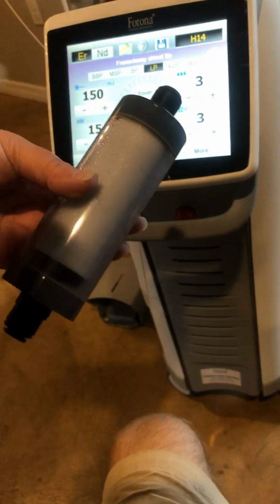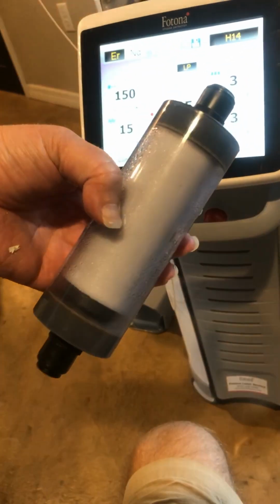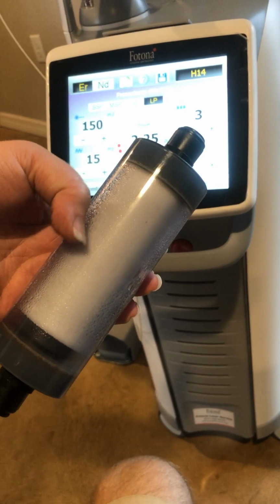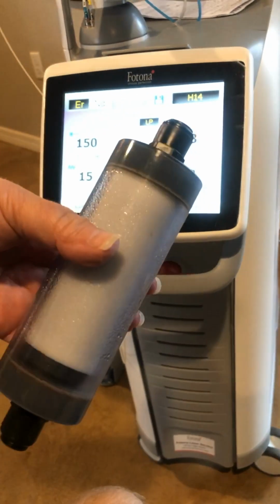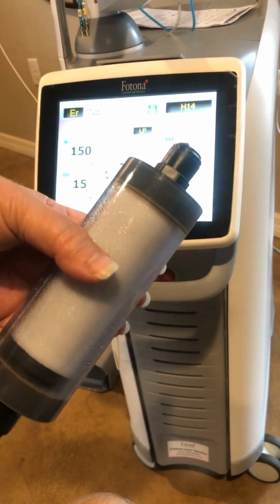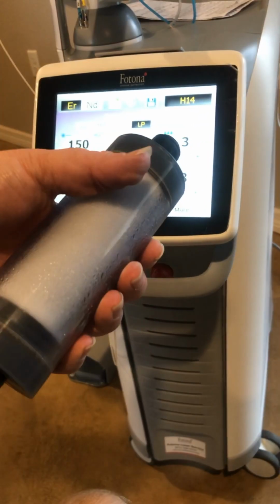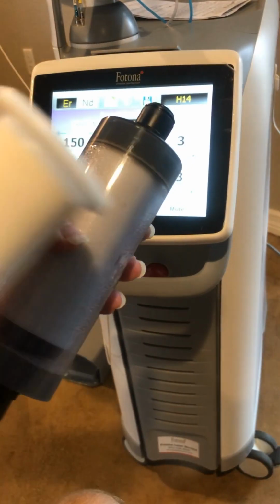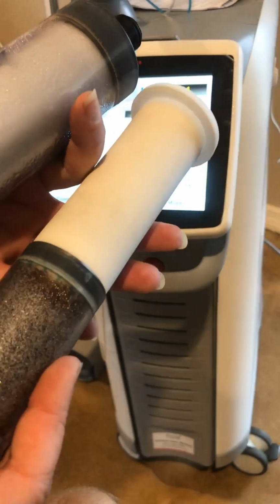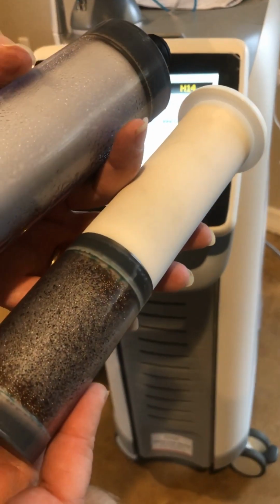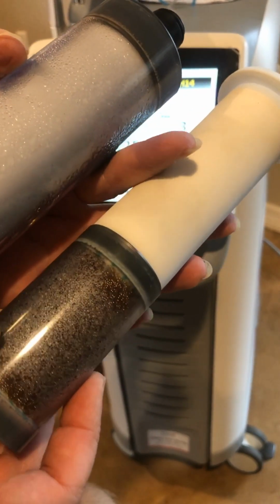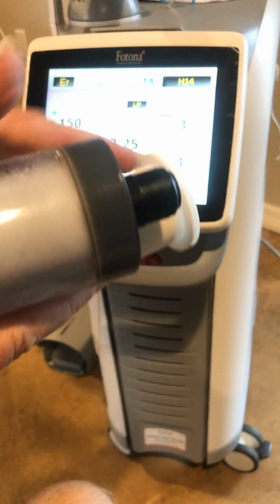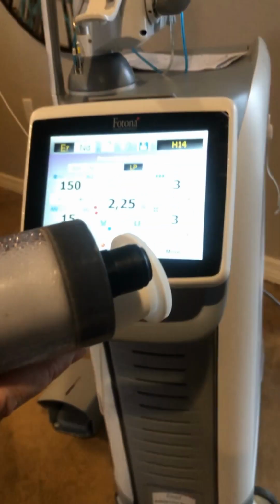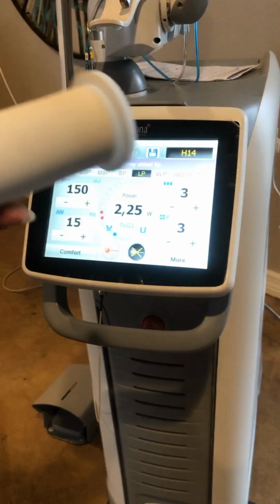And those filters, this at one time was pure white like snow. And the metals and the debris and things that are even inside the distilled water, it's inside the machine, eventually clogs that up. And as this gets clogged, it's going to leave heat. Same thing with this. They'll only last for so long. And so the preventive maintenance is to keep these and to keep your whole mechanism inside running at top shape so that you can have your machine last as long as you can. And it's as easy as that.